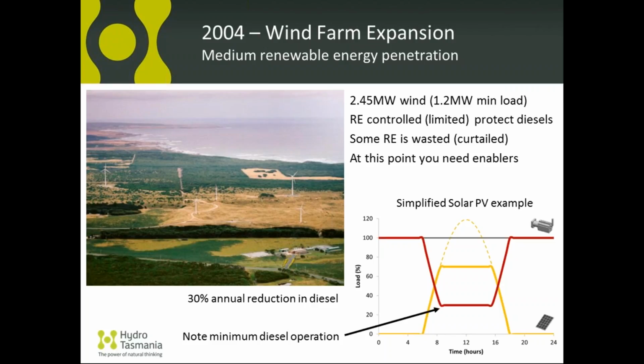Essentially what this shows is that we have to clip the renewable generation so that when we ask our diesel generators to cover the remaining load, we don't push them down too low in their generation output. Diesel engines can only reduce production to about 30% of rated capacity, so we have to protect those engines and operate them over a normal range, which means limiting the renewable energy put into the system. This maintains reliability, but it also means there's more diesel displacement we could achieve with a better integration mechanism. Still, at this point we had a 30% reduction in diesel fuel use, which is fantastic.